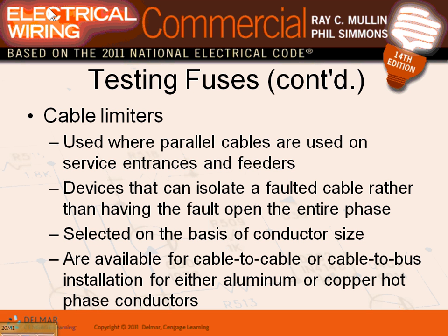Cable limiters. Guys, I'll show you where to use cable limiters. If you have multiple runs and network ties, they put in cable limiters. A cable limiter has short circuit capability only. So if it sees a short circuit, it will trip. It wouldn't trip on a ground or on an overload. So it looks at short circuit only. If you have multiple phases, it will isolate that phase. I'll show you a nice picture.